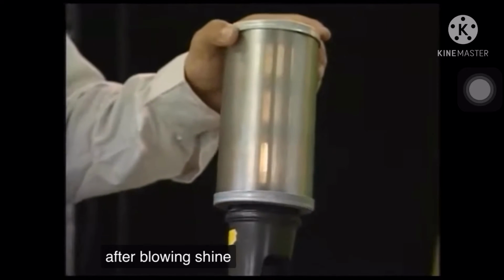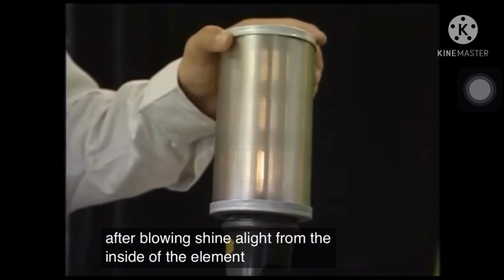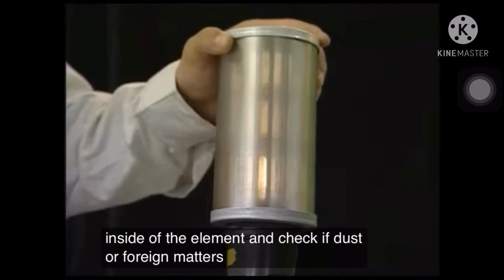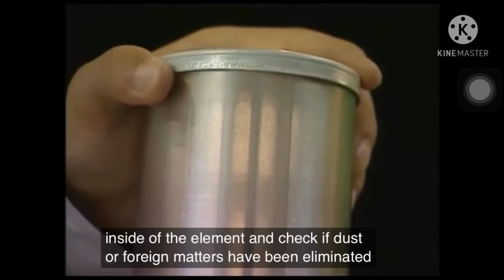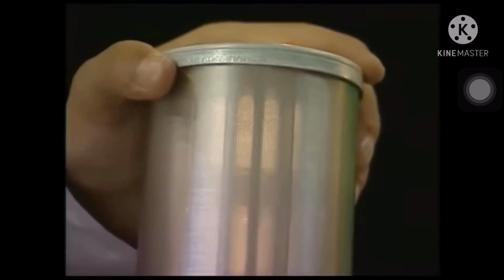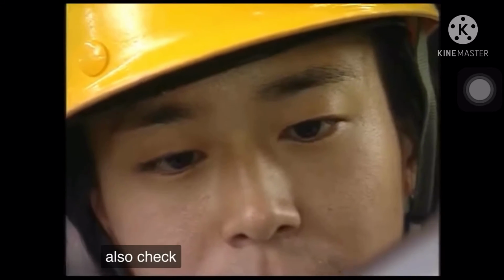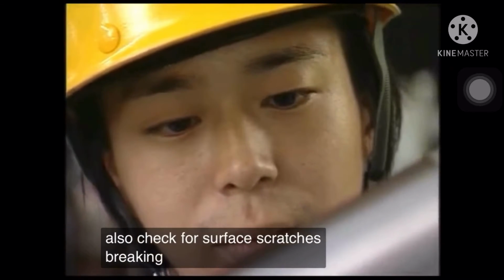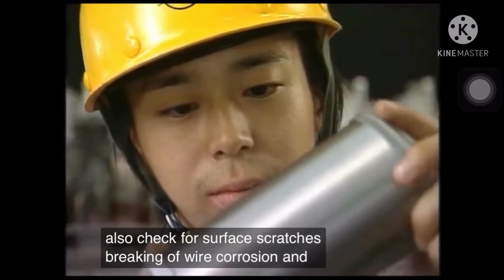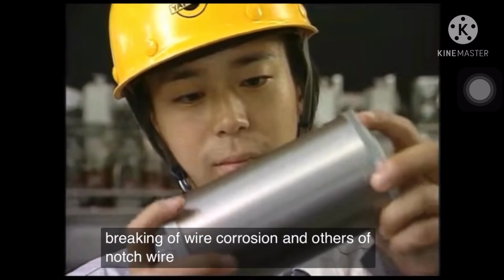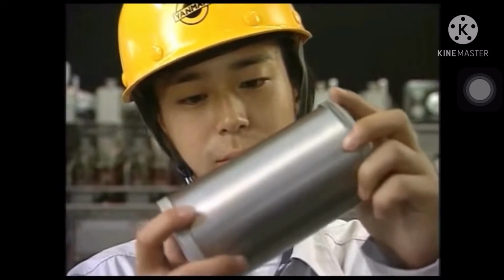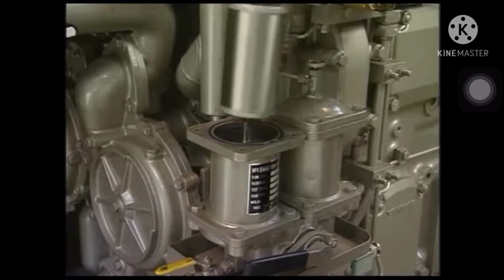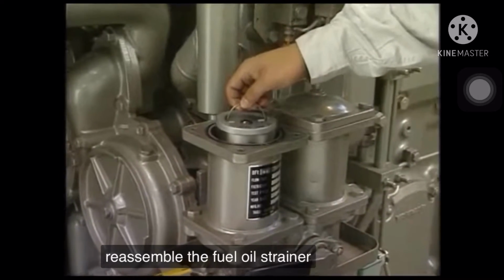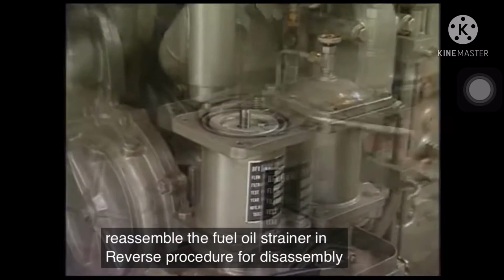After blowing, shine a light from the inside of the element and check if dust or foreign matters have been eliminated. Also, check for surface scratches, breaking of wire, corrosion, and others of notch wire. Reassemble the fuel oil strainer in reverse procedure for disassembly.